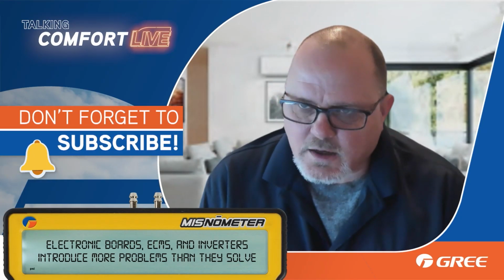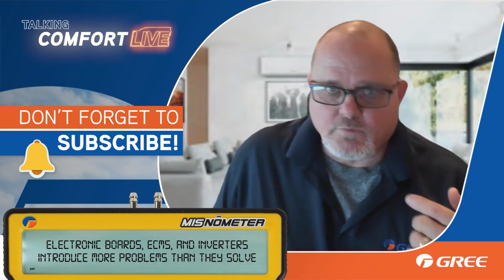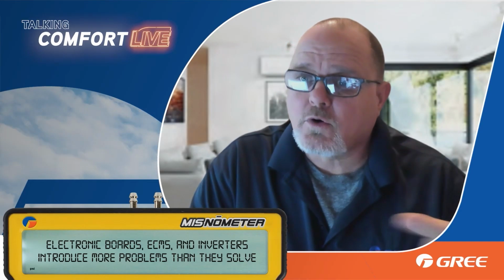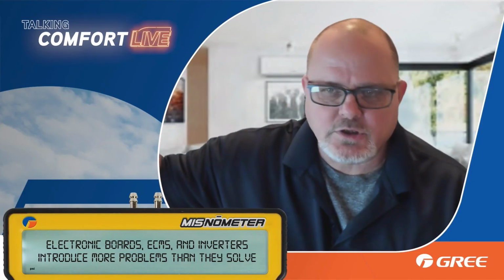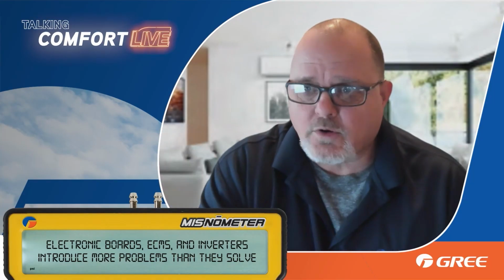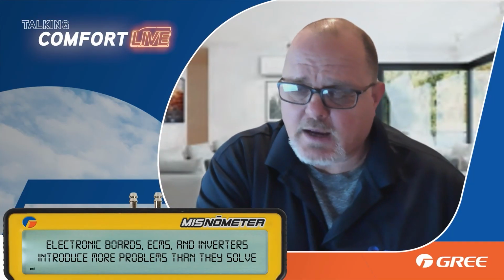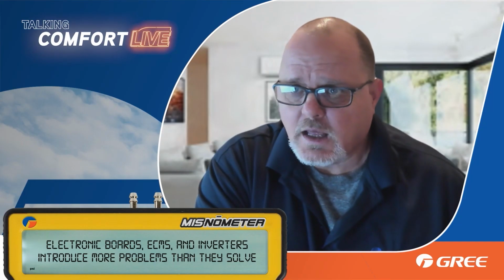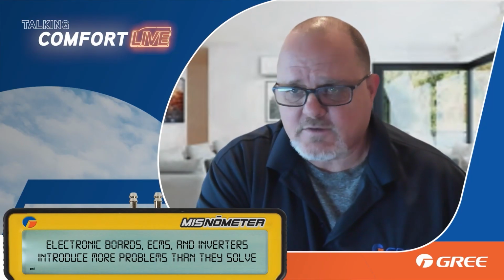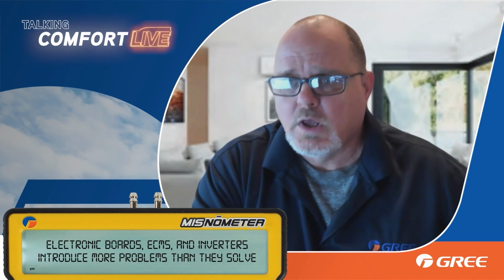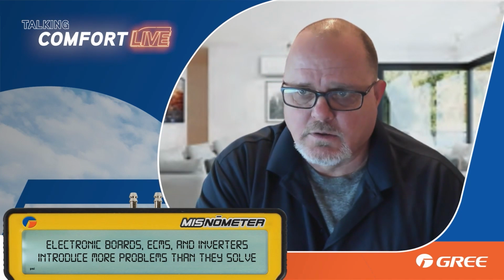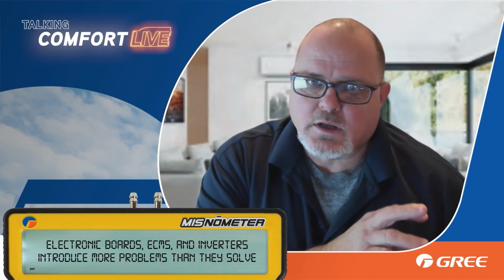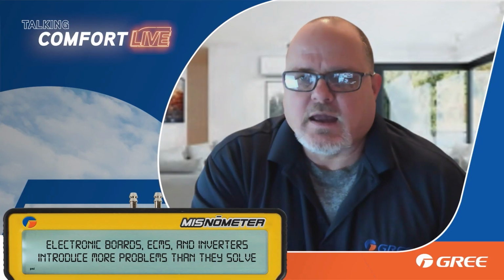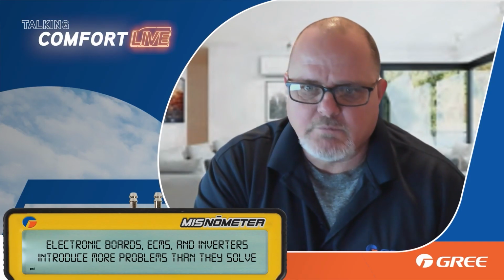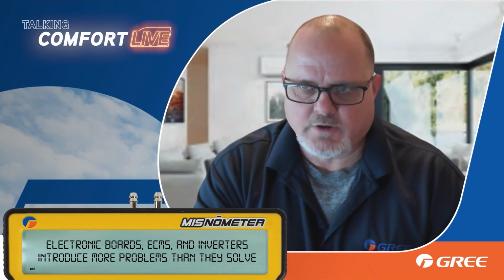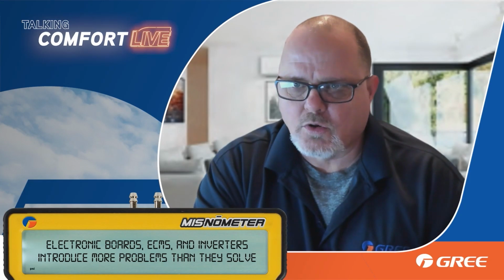the compressor's stuck, so many people think of locked rotor amperage as this really high amperage, which is where the term locked rotor amps came from, because you had PSC compressors that truly had a locked rotor amperage rating, because that's the maximum amount of amps that compressor can pull to get it to start from a dead stop, right? Well, when it comes to inverter-driven equipment, they don't have that, as we talked about with a variable speed blower motor or an inverter-driven compressor. They start out at very low amperage and slowly speed up.